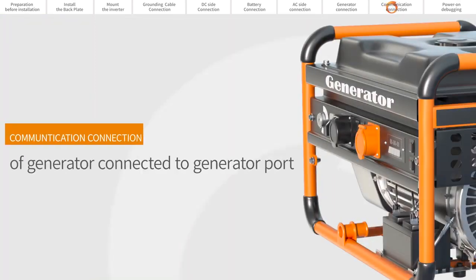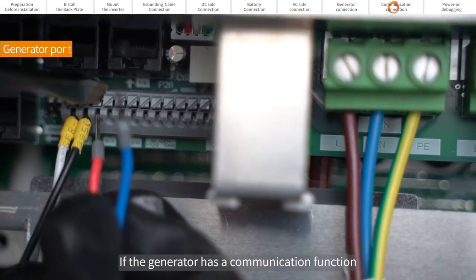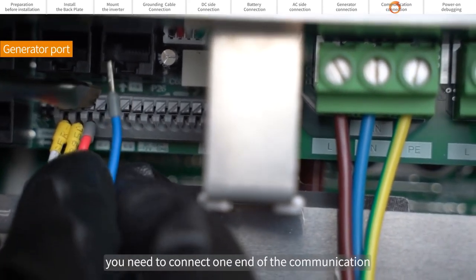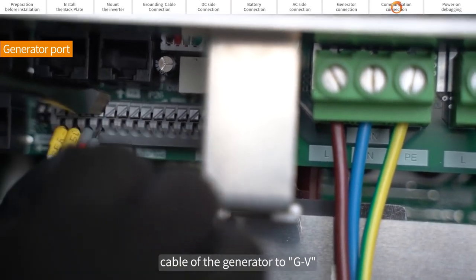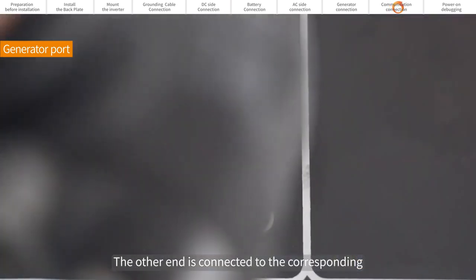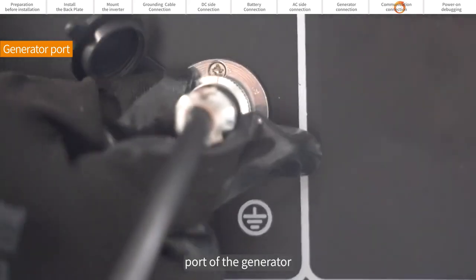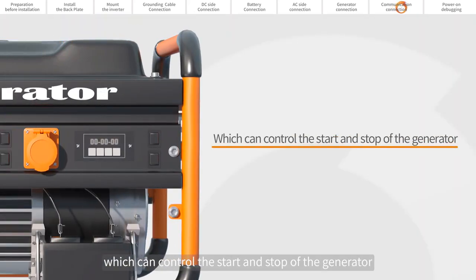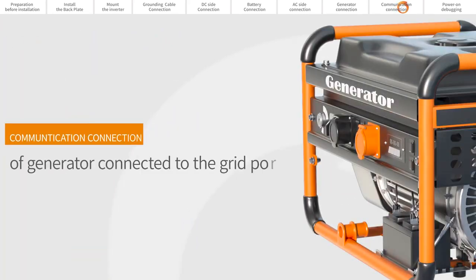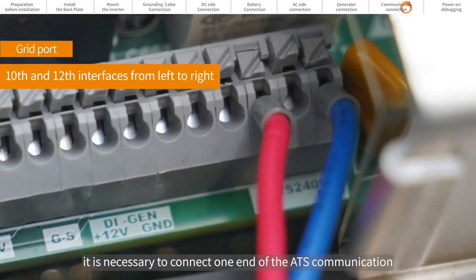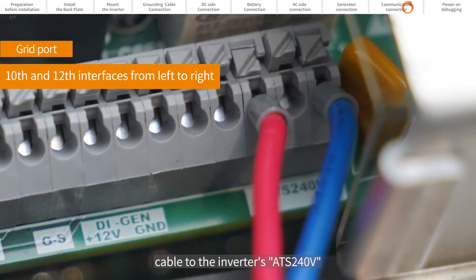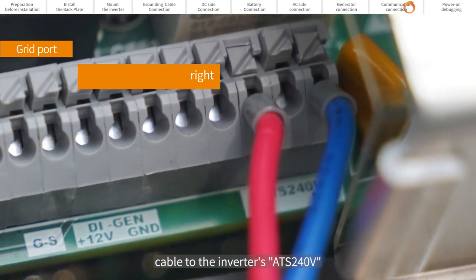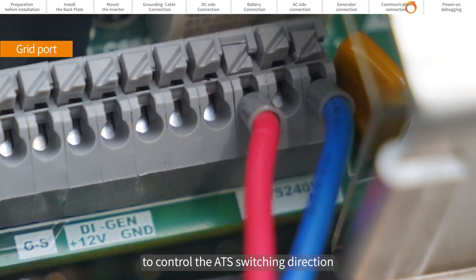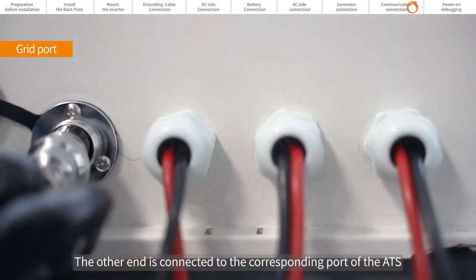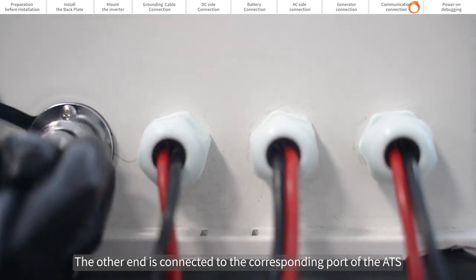Communication connection of generator connected to the generator port. If the generator has a communication function, you need to connect one end of the communication cable of the generator to GV. The other end is connected to the corresponding port of the generator, which can control the start and stop of the generator. Communication connection of generator connected to the grid port. It is necessary to connect one end of the automatic transfer switch communication cable to the inverter's ATS-240V to control the automatic transfer switch switching direction. The other end is connected to the corresponding port of the automatic transfer switch.